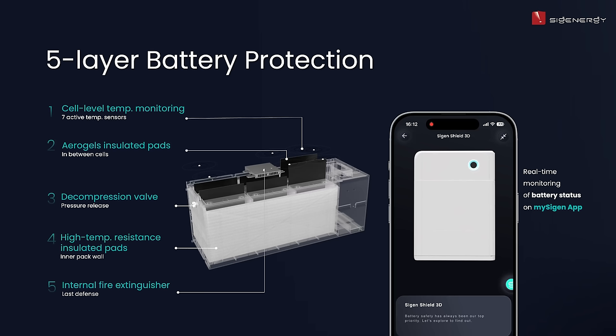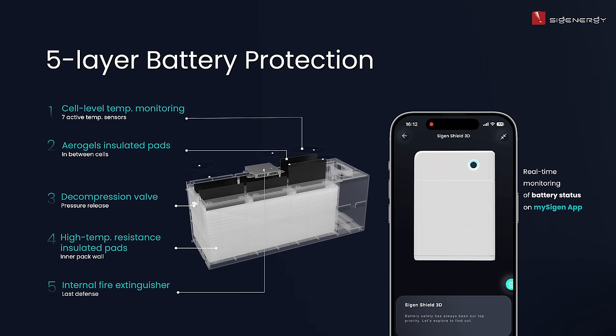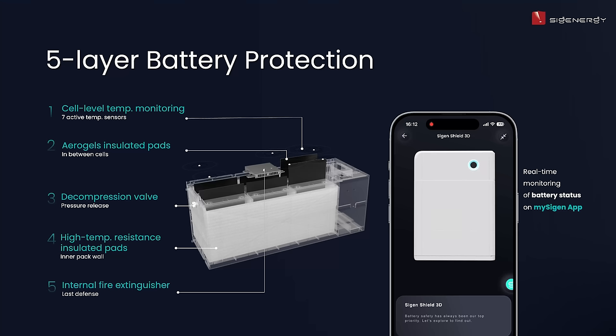Then we have aerogel insulated pads between each cell, which reduces the heat transfer between cells and reduces the overall operating temperature inside. If hot gases do build up as the heat rises, and it gets past that level, we've actually got a decompression valve which will open up and expel that gas, which will then cool things down. We've got high temperature resistant insulated pads on the inner pack wall between the cells and the inverter casing. And then the last level of defense, if it gets to that stage, which I'm pretty sure it's not going to, each battery actually has a fire extinguisher built into it.